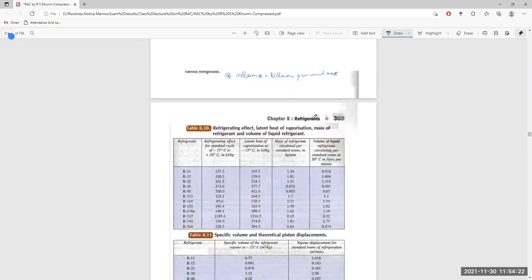The chemical properties of the refrigerants include flammability, the tendency to burn. We have discussed the hydrocarbon refrigerants, which are highly inflammable. Ammonia is somewhat inflammable and becomes explosive when mixed with air in the ratio of 16 to 25 percent of gas by volume. The halocarbon refrigerants are neither flammable nor explosive.